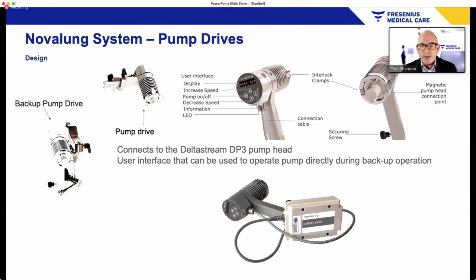The design is such that it dissipates heat in a very small fashion, and you don't need two consoles to run the drives. We have two drives that can be run off of one console. And here's another image that shows the batteries can be connected directly to a pump drive in an emergency, and you can operate the RPMs directly from the back of the motor drive.